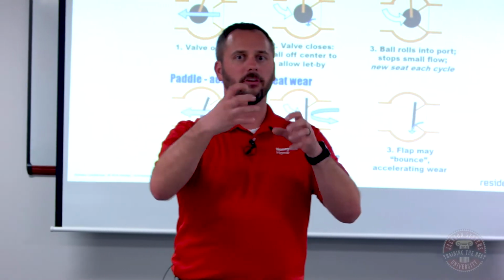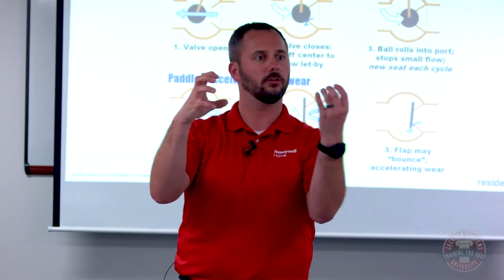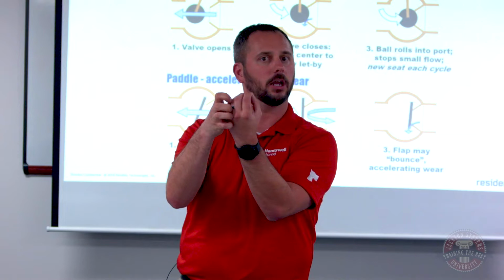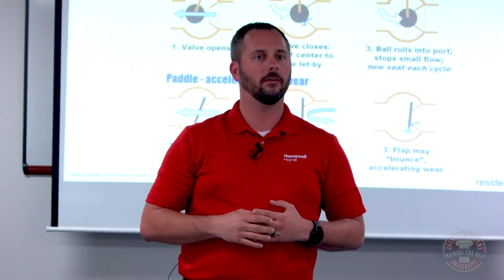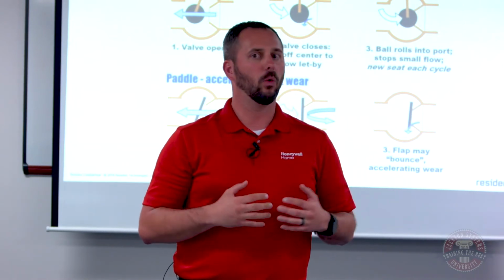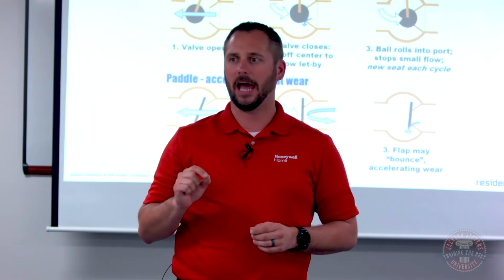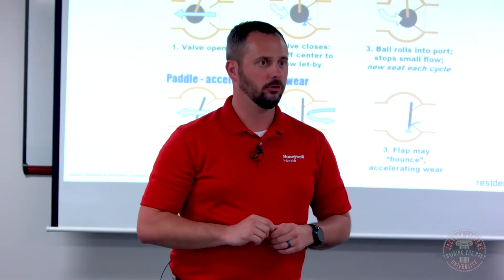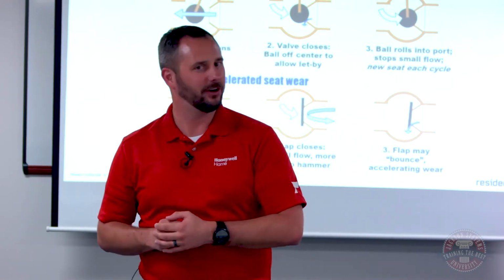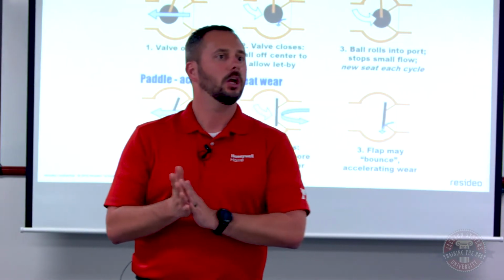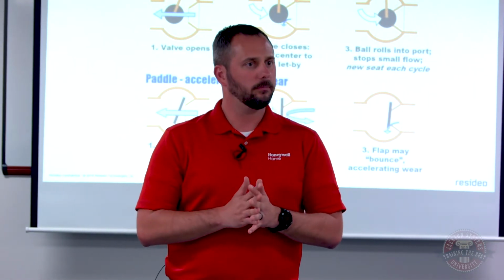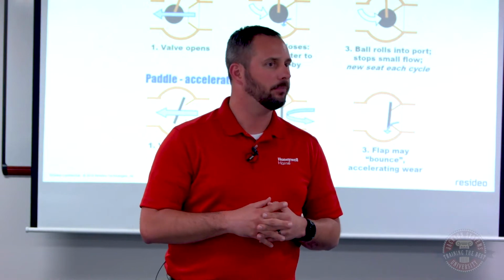But on ours, it's a ball basically sealing on a cup. So there's not a whole lot of potential for water hammer, but our 1000 series valves can still have some water hammer. So if you're getting it, and that's why I was asking if it was our valve or not, if you're getting it on our valve, you may want to take a look at the system. There may be something else that's causing that. But, I lost my clicker.